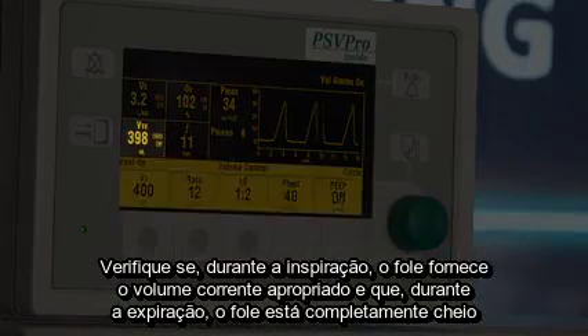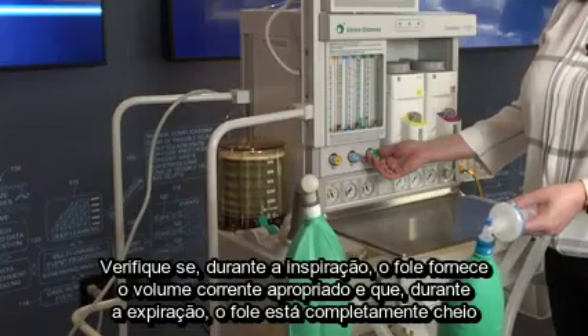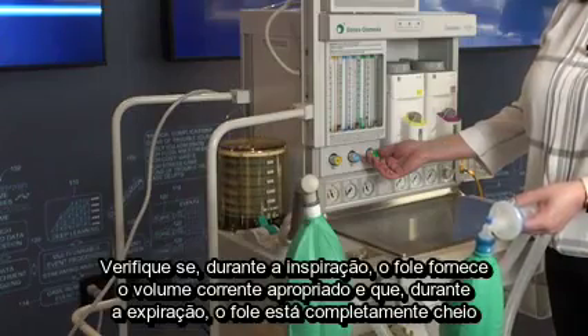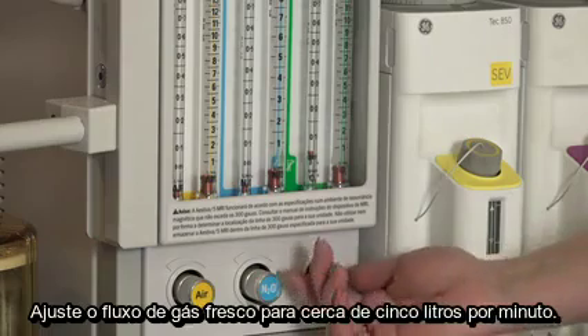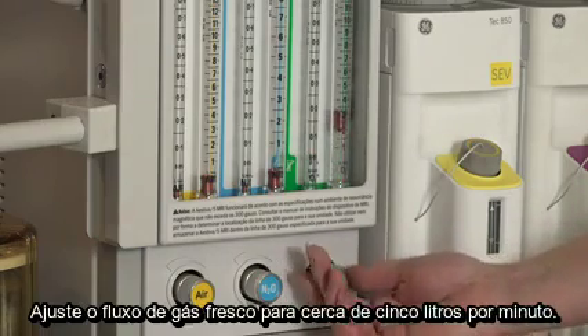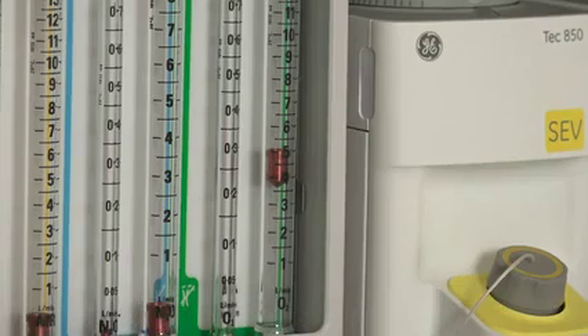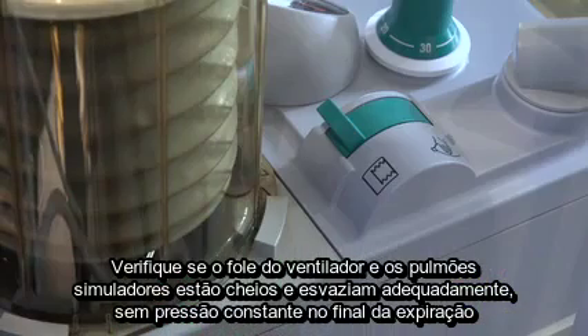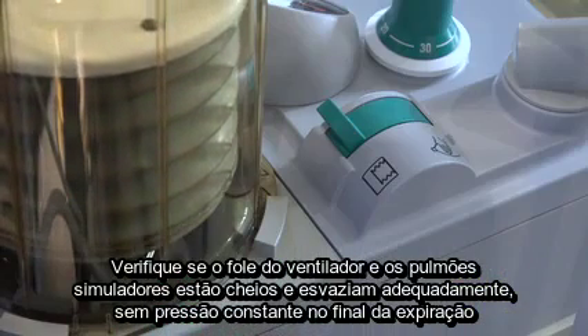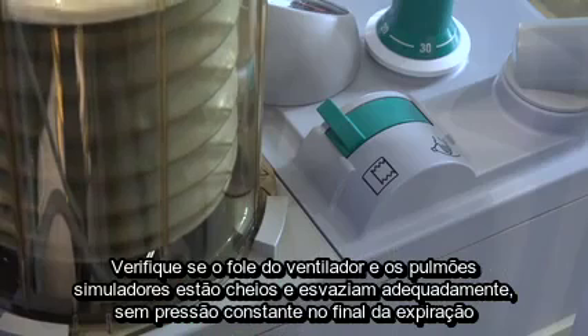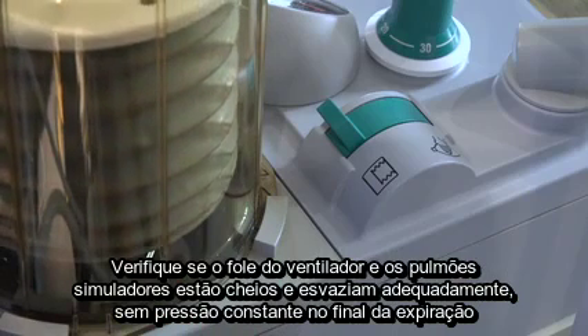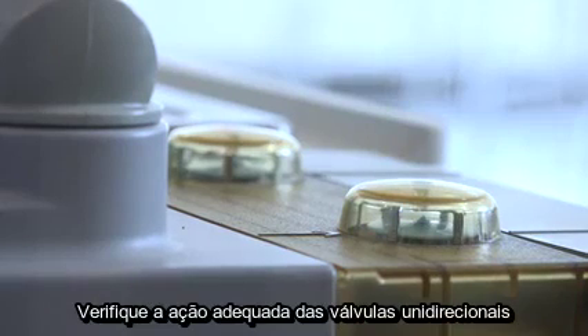Verify that during inspiration, the bellows delivers appropriate tidal volume and that during expiration, the bellows fills completely. Set your fresh gas flow to about 5 liters per minute. Verify that the ventilator bellows and simulated lungs fill and empty appropriately without sustained pressure at end expiration. Check for proper action of the unidirectional valves.